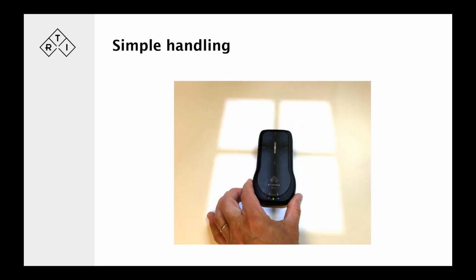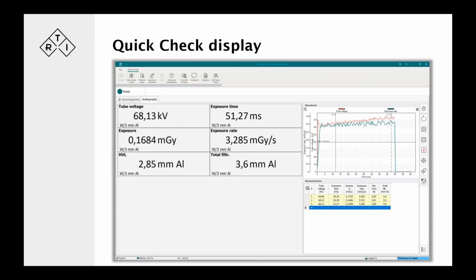Handling is pretty simple. I just made a picture here just for scale. Place it in the beam, power it on, and you see that the status indicator goes green. You have a blue for Bluetooth, because there are no cables attached to this one, because many of our users are happy with using the Bluetooth connection, which does take some time in setup. Once that's done, make your exposure, and you get the data. The data is then transmitted via the Bluetooth link onto software which we call QuickCheck. It's a display that shows the values of the latest exposure. We have waveforms, and there is also a log or a grid that shows you all the exposures made during that on-off cycle in QuickCheck.